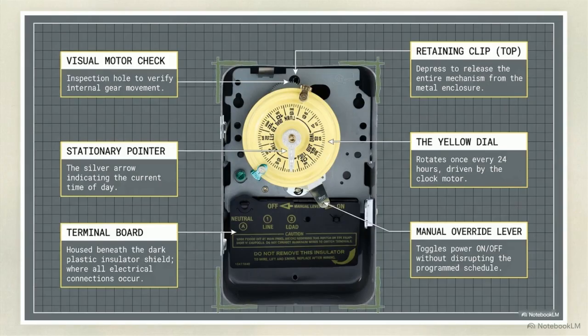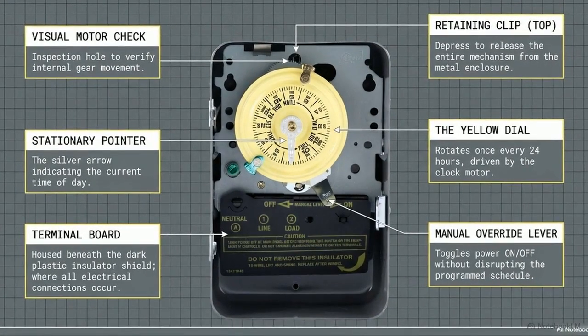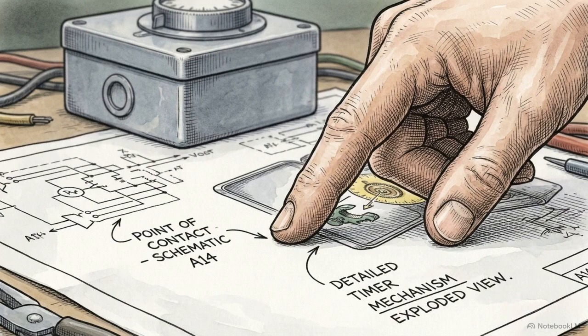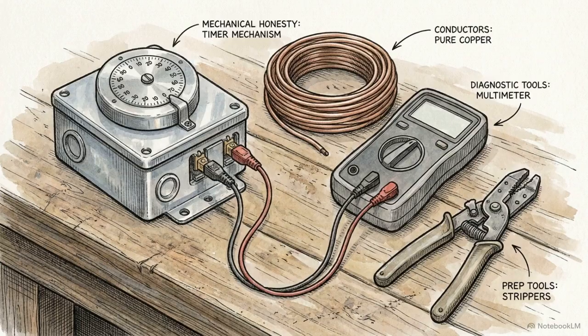Assuming you have the right model, let's map the core anatomy. You will be manipulating 3 main components: the yellow 24-hour dial, the stationary pointer that indicates the time of day, and the terminal board housed beneath the bottom shield. Verifying your voltage matches your equipment and knowing exactly where these components are located ensures you won't damage the timer before the physical installation even starts.